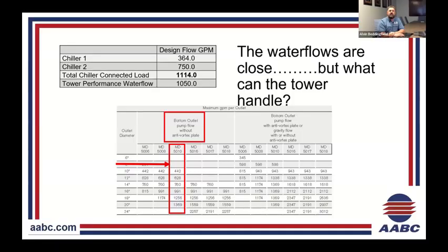So contacting the mechanical contractor, he met me out there at the project and we walked through the engineering submittal and what the tower can do, and identified to him, hey, the tower's not configured correctly. The piping's completely wrong. We can't be off the bottom. We're not even on this chart anymore of what the tower can actually drain, which is why we are sucking air. We drain that whole tower completely dry, and then there's no water in the back into the pumps, and it just starts going dry, which then gravitates into the chiller.